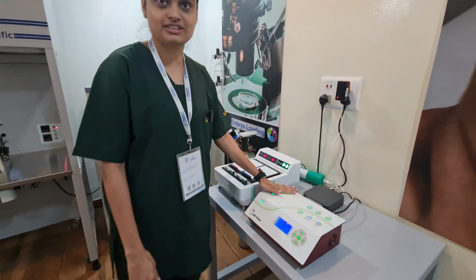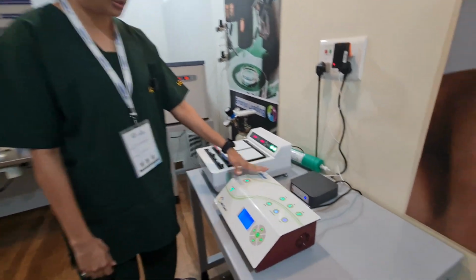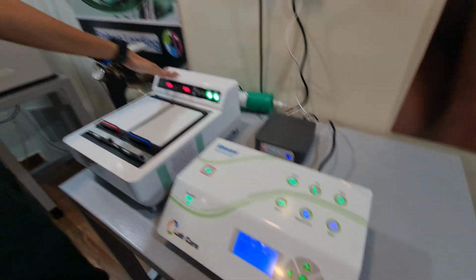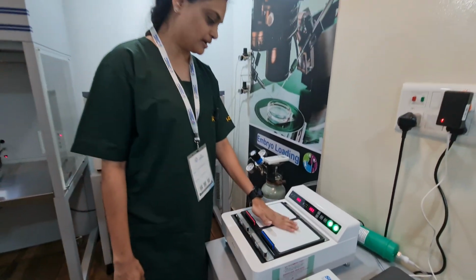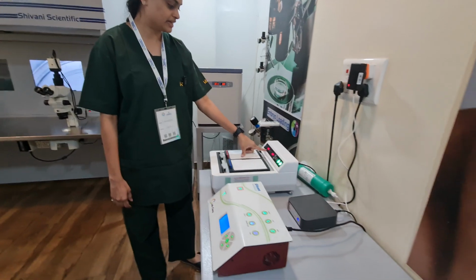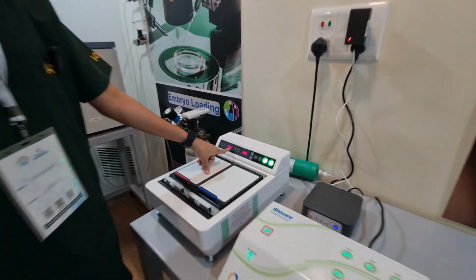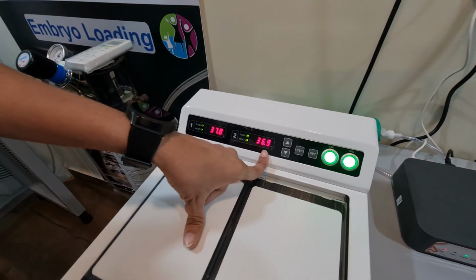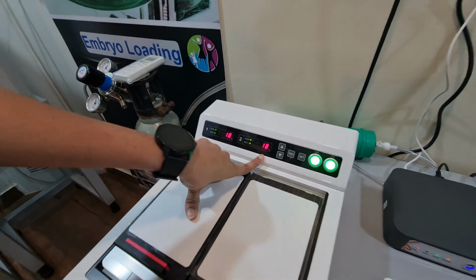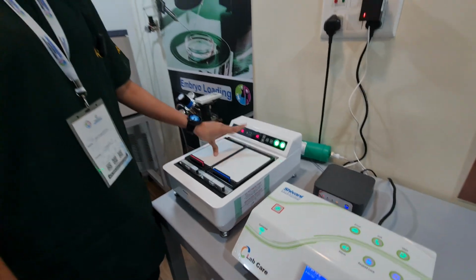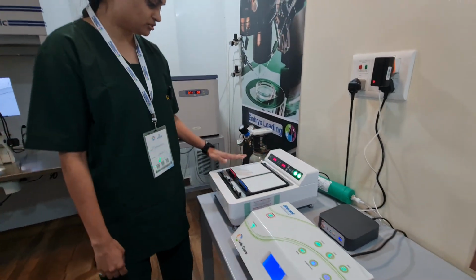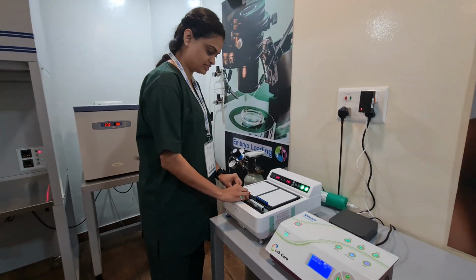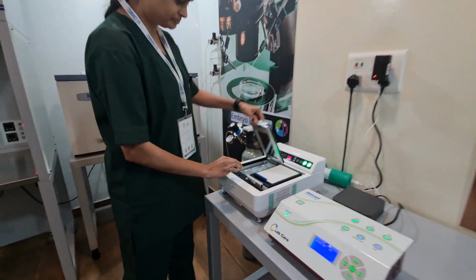So here, this is the lab care system. It's from Shivani. It's connected to our incubator right now. We can see there are two chambers and we can see the temperature, which is 37, and for the second it is 36.9. We can see the flow, it's 18, the same for both the first and second. What we will do is, we'll just open the first and see if there is a fluctuation.